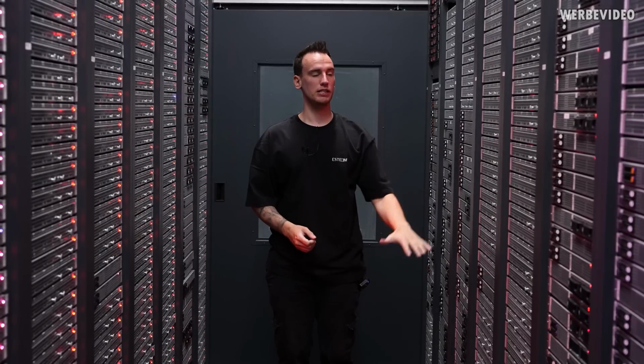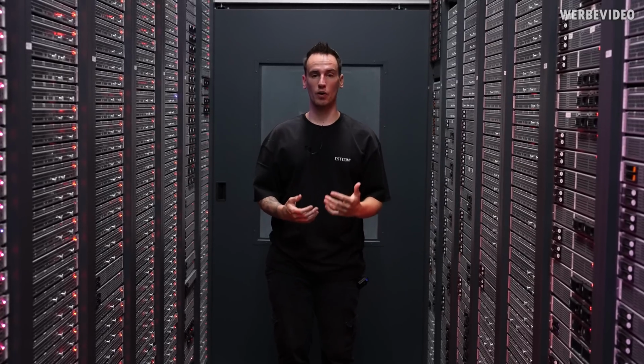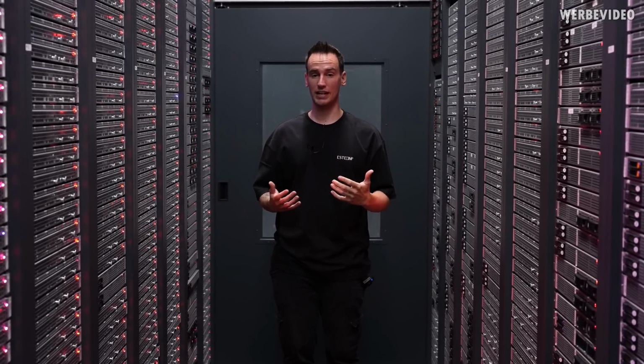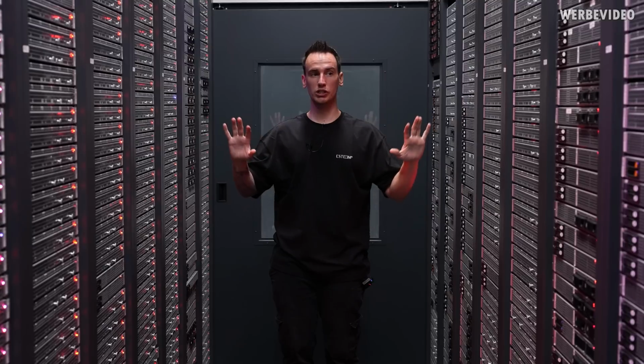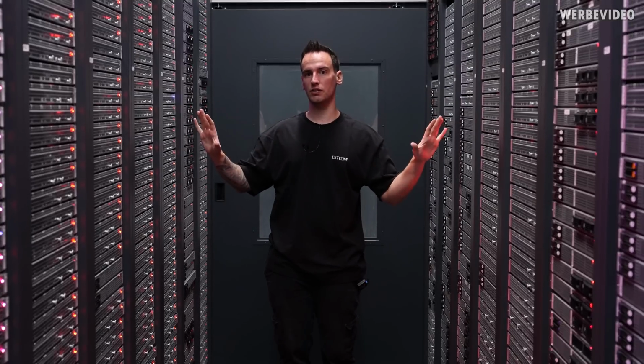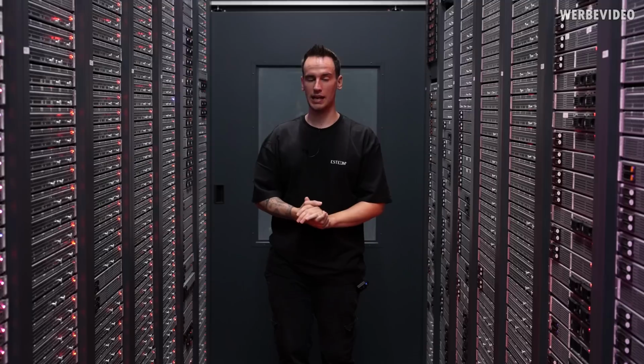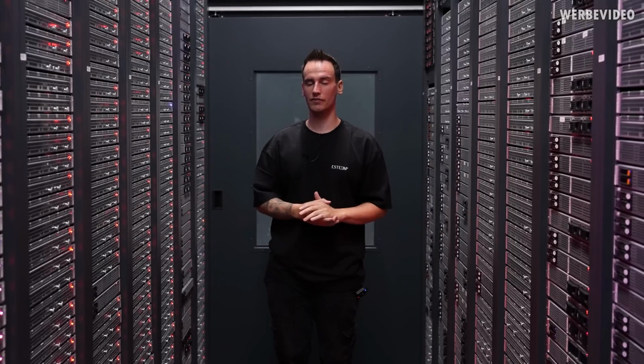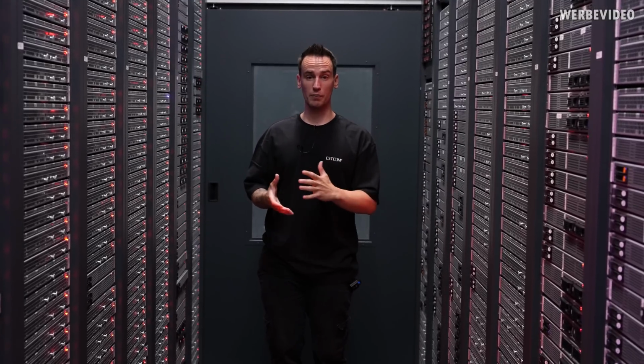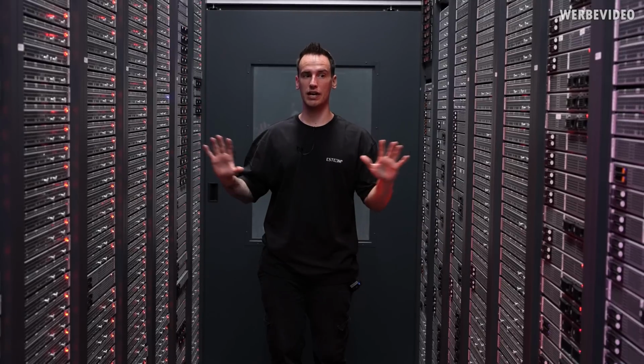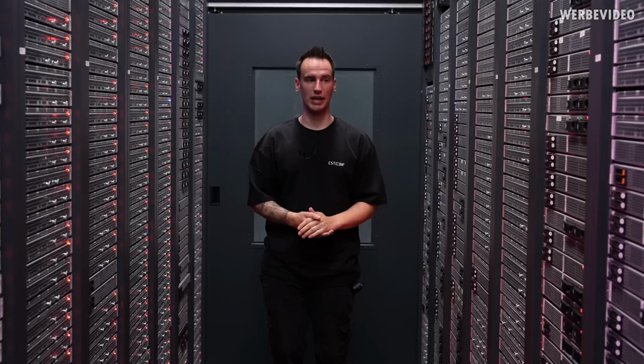One of these racks right here can be supplied with a maximum of 11 kilowatt of energy. We have two huge server rooms in this data center right now, and each of the rooms can be supplied with about 650 kilowatts. So a total of about 1.3 megawatt for the entire data center which we're visiting today.